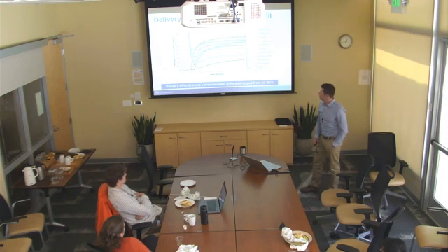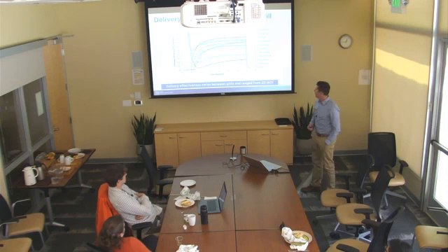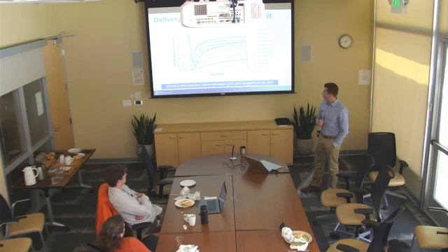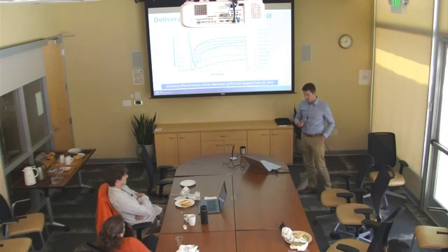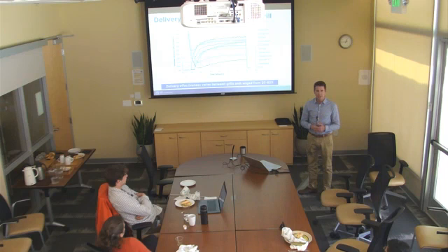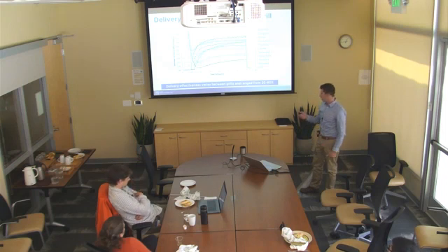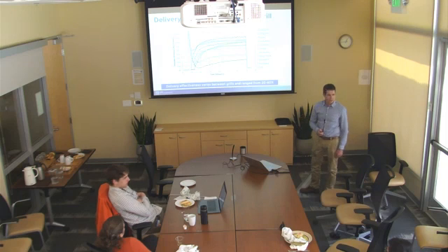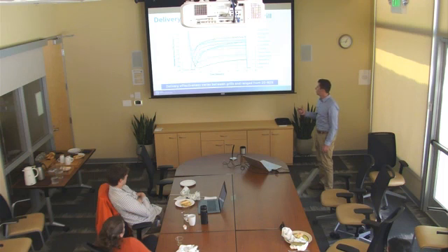So here are some of the results. This is the delivery effectiveness for one of the homes in the PG&E territory, showing the delivery effectiveness for every grill of that house during a situation where the equipment was running at 100% speed and all the ducts were open. So it's kind of a single speed scenario, or a full-out scenario. All I'm showing here is that the delivery effectiveness is significantly different between the different ducts. You have some running at 20%, which is terrible, right? And then there's a cluster of them up here in the 60 to 80% range.